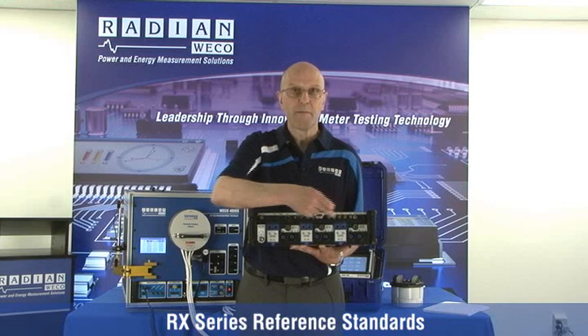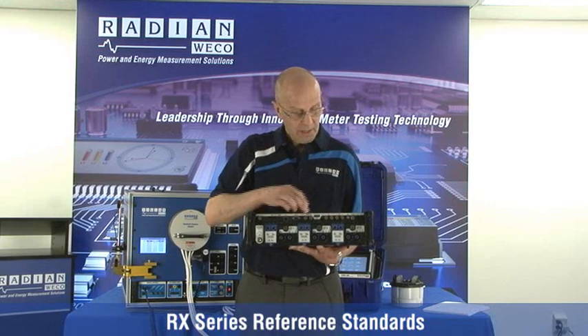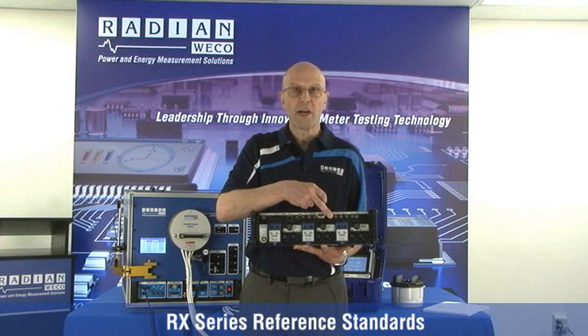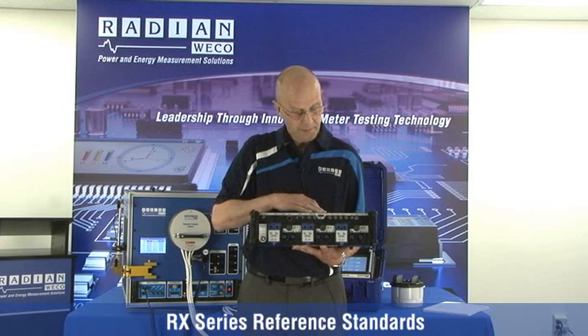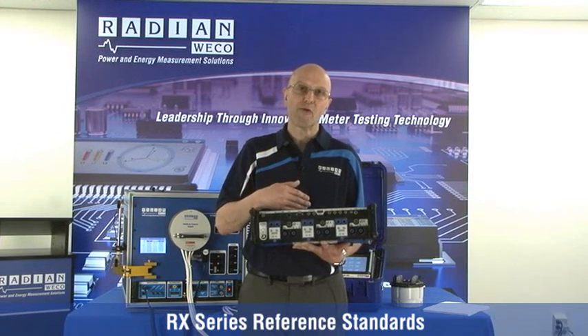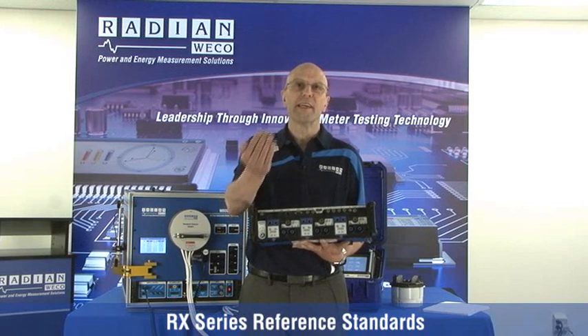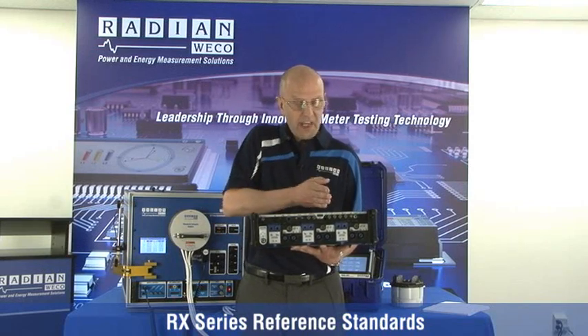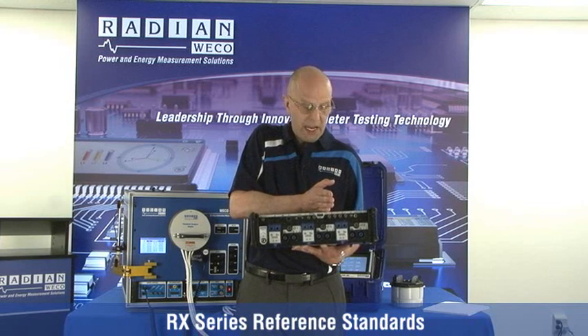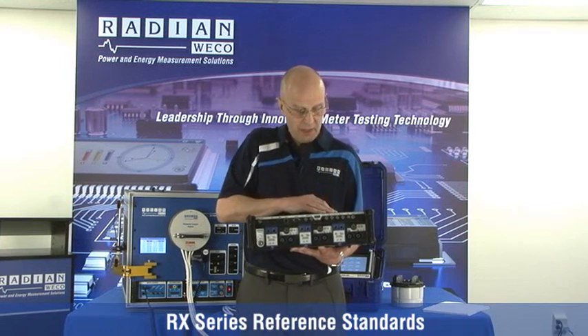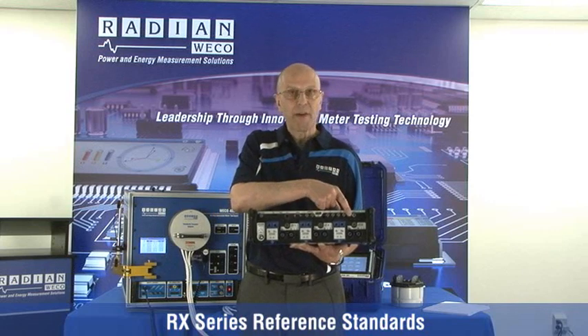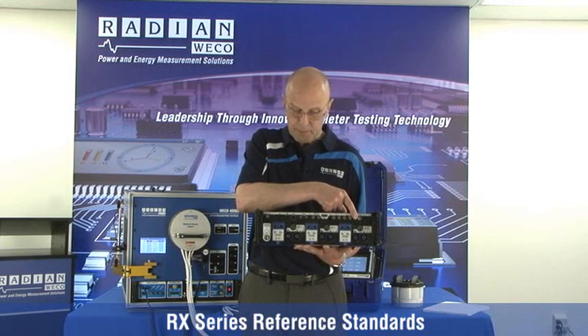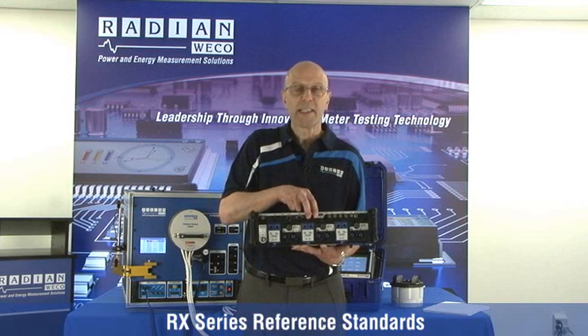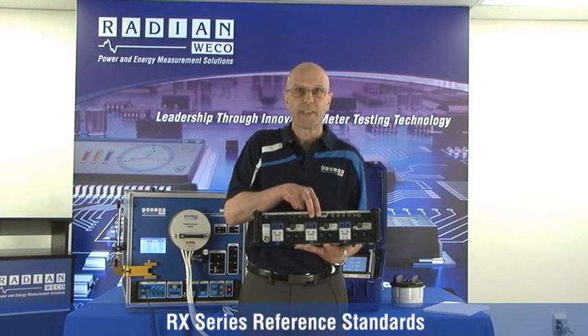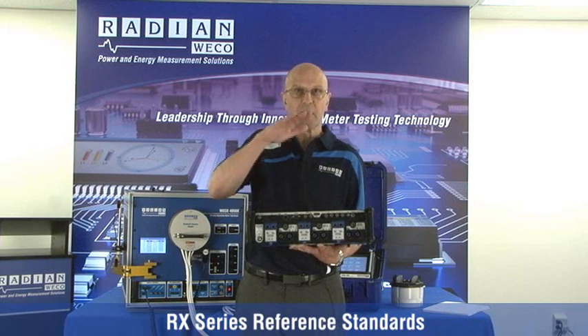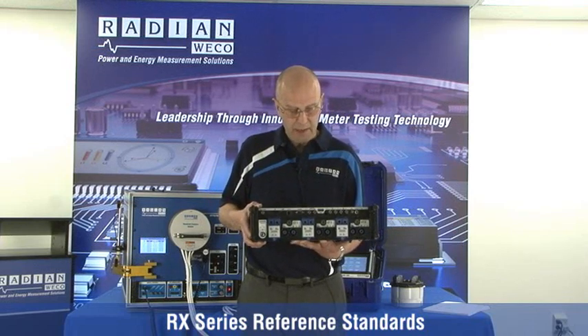Here you see a number of BNC ports. The 4 ports here are primarily used as programmable pulse ports. Programmable in the sense that they are programmable output pulsing or can input a pulse. Setting the KE value or KH value or setting the direction of pulse is available to you. We have a pulse pickup port for optics. We have 2 BNCs here for a reference input and reference output. This is to frequency lock a number of Radian standards together.